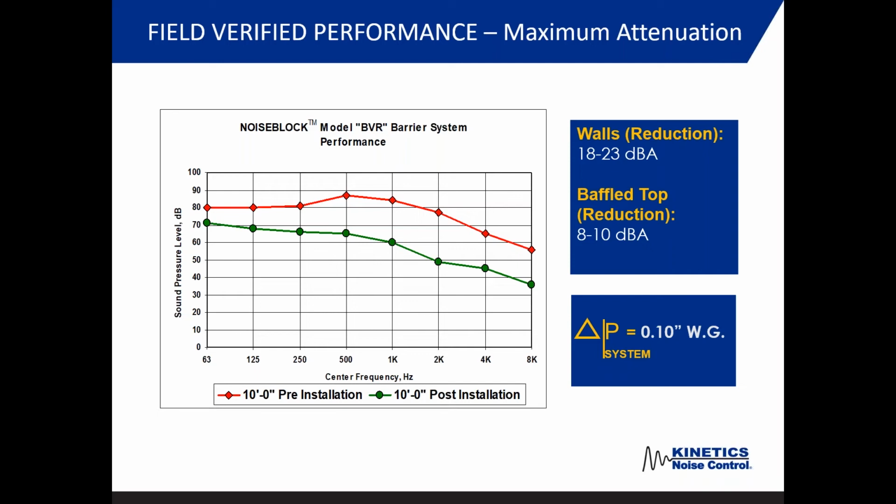Now, we look at from the intake, just upstream of the intake external to the enclosure on the acoustic louvers, to just downstream of the upblast fans beyond the pergola baffles, of about a tenth of an inch pressure drop. So typically in applications of these air-cooled chillers, it can take that without degrading the performance or voiding the warranty of the chiller.